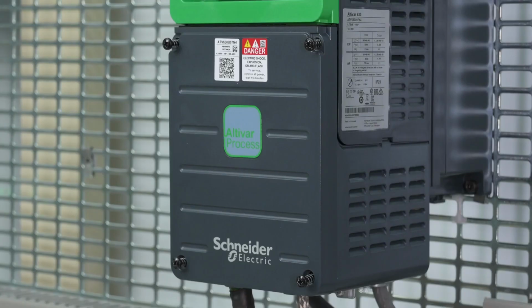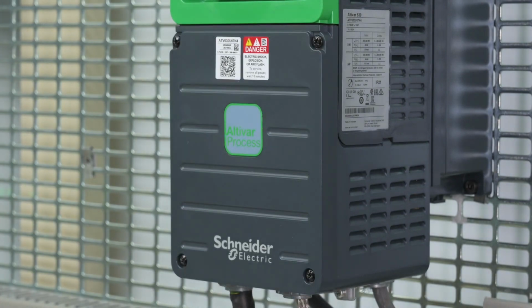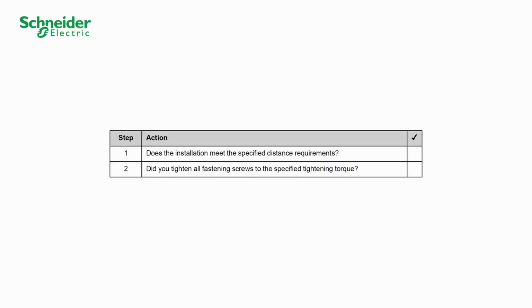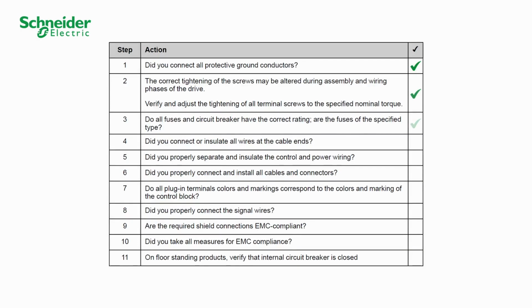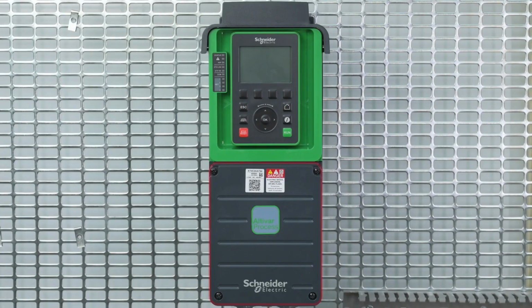Once the wiring is done, replace the cover on the drive. Tighten the 4 captive screws. Before switching on, use the checklist available on the product installation manual. Start with the mechanical part installation. Continue by checking the electrical installation. Finish by checking the covers and seals.